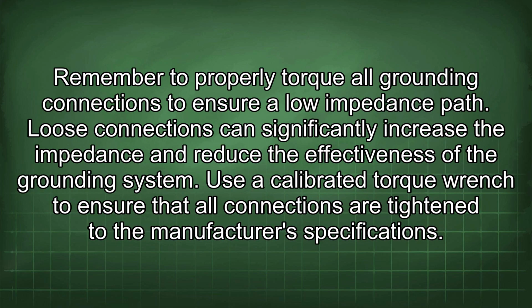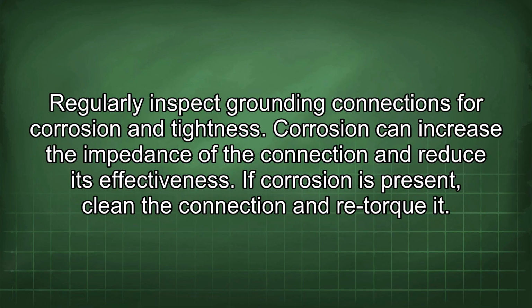Remember to properly torque all grounding connections to ensure a low impedance path. Loose connections can significantly increase the impedance and reduce the effectiveness of the grounding system. Use a calibrated torque wrench to ensure that all connections are tightened to the manufacturer's specifications. Regularly inspect grounding connections for corrosion and tightness.